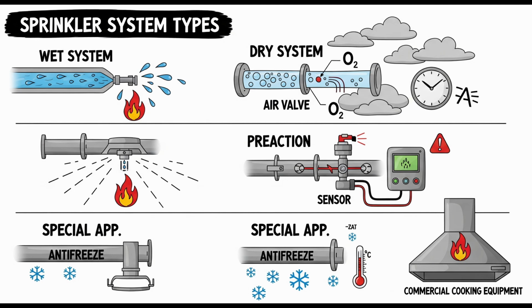No. You'd think, but it's critical to get all of it out. Pendant sprinklers, by design, have low points where small amounts of water can get trapped even after draining. If you hydrotest with plain water and then fill the system with antifreeze solution, any trapped pockets of plain water in the pendant heads or low spots in the piping will still freeze solid when the temperature drops, even if the surrounding liquid is antifreeze. The pure water pockets will freeze inside the antifreeze. Exactly. This can damage the sprinkler head or burst the pipe. Completely draining all the water, or better yet, testing with the actual listed antifreeze solution itself, prevents this risk. Get every last drop of plain water out.